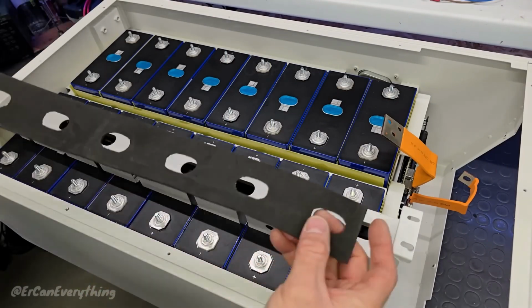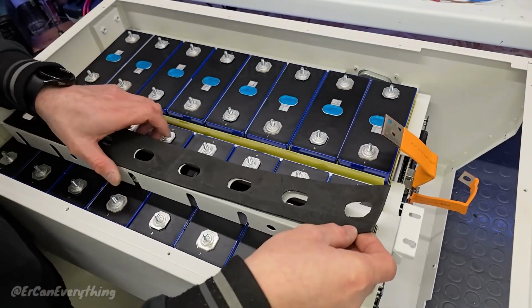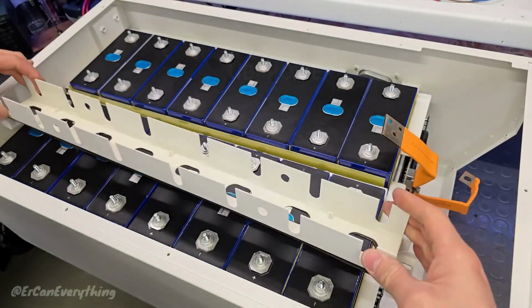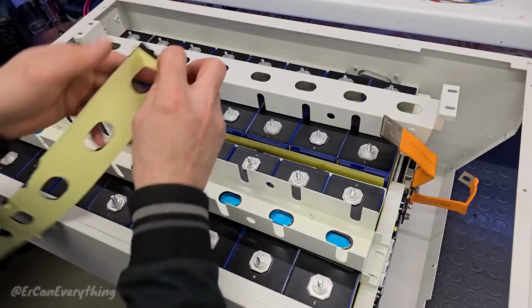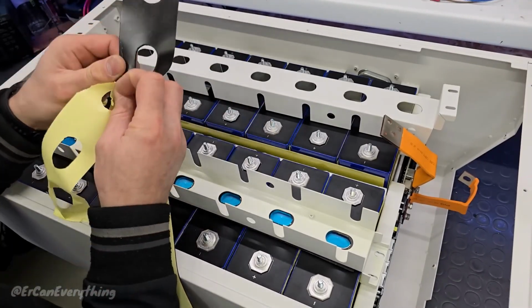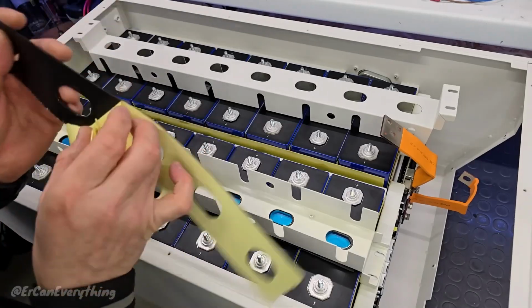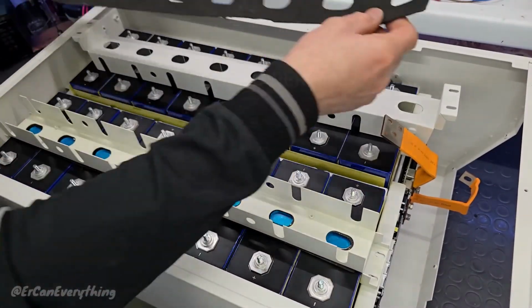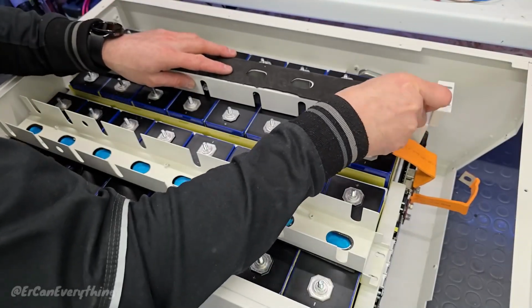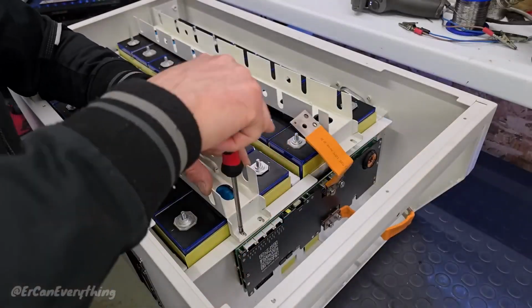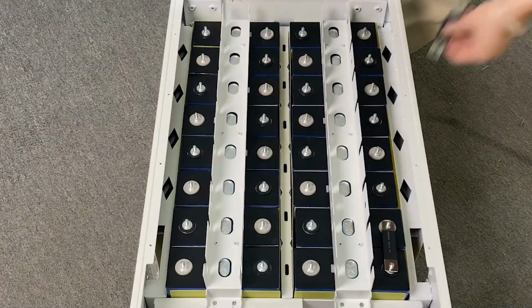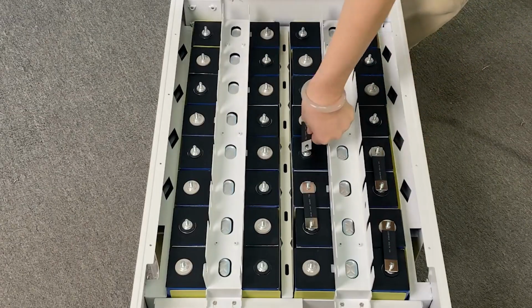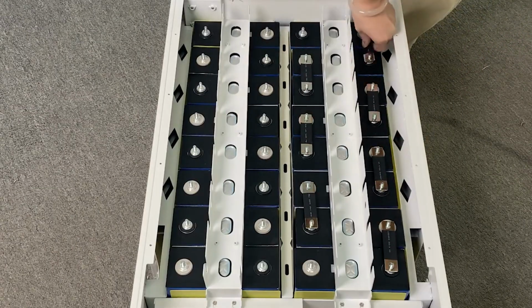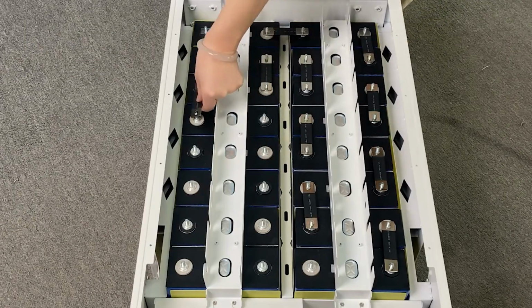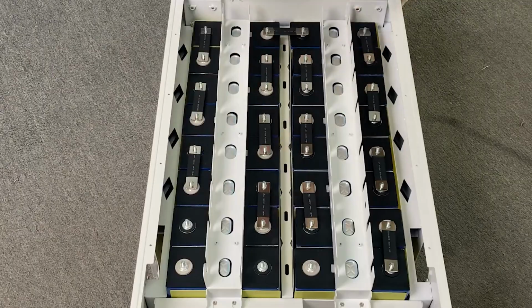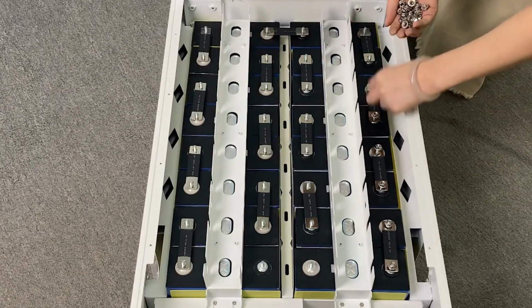Apply the isolator strips to the cell hold-down bars and reattach the hold-down bars with the previously removed screws as shown in this video. Next, apply the cell bus bars exactly as they are shown in this image. Applying the bus bars in any other configuration will cause a dangerous short circuit. Next, loosely apply the cell terminal nuts to keep the bus bars in place.